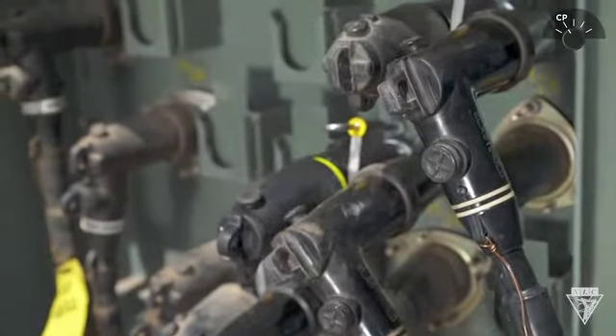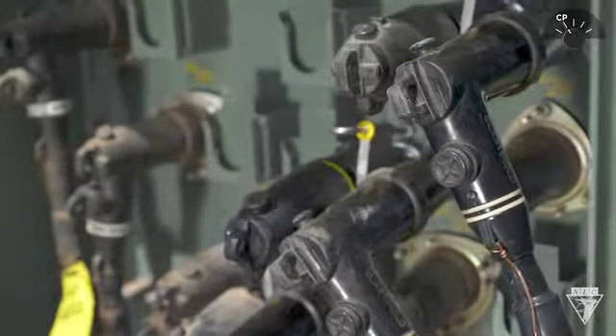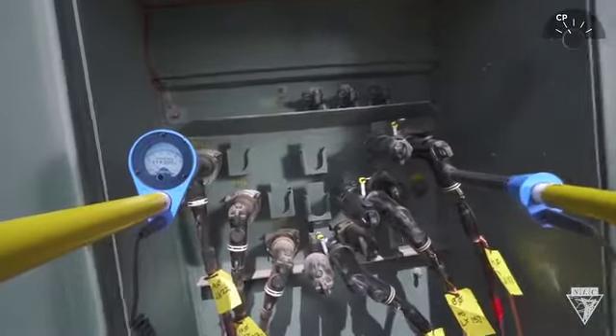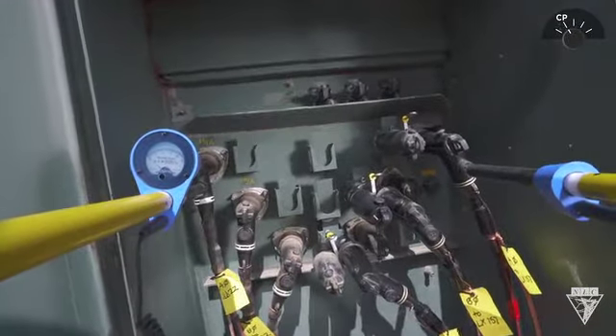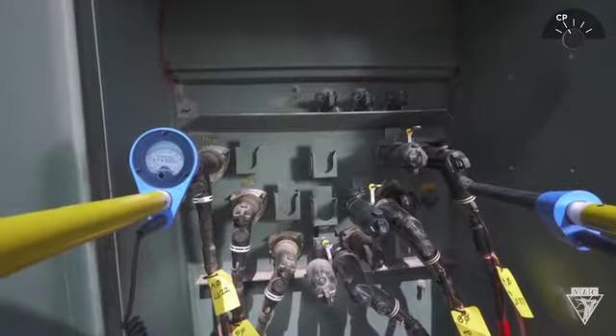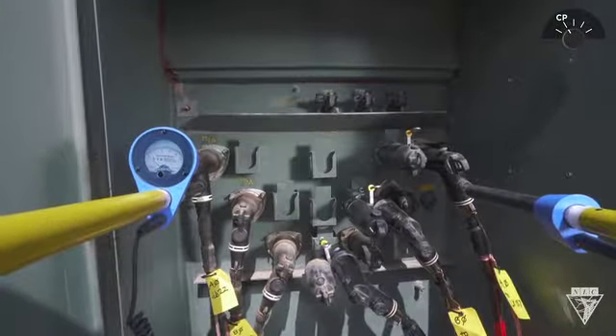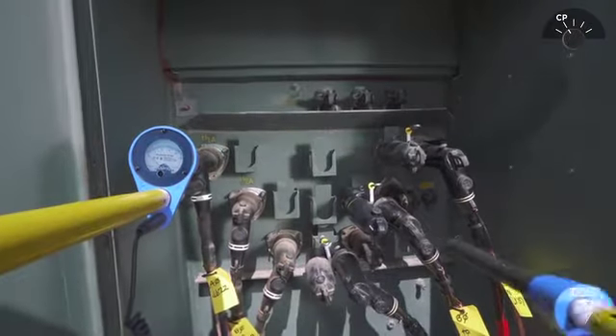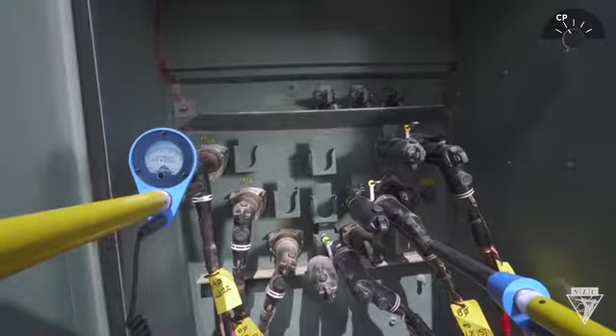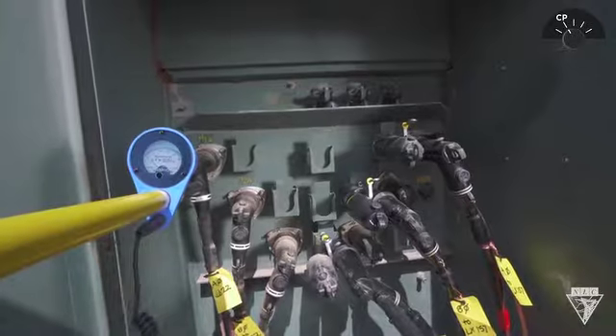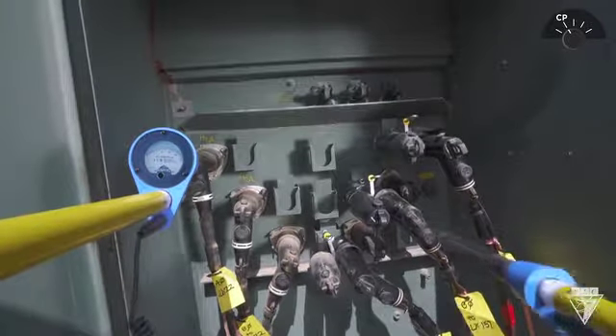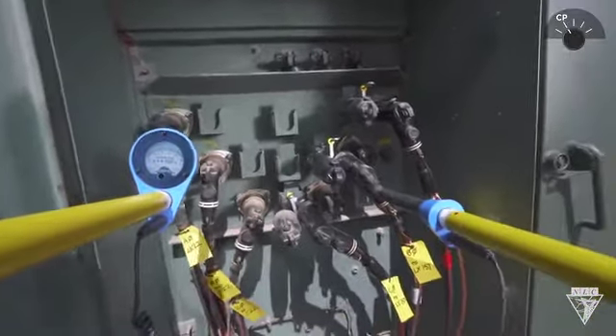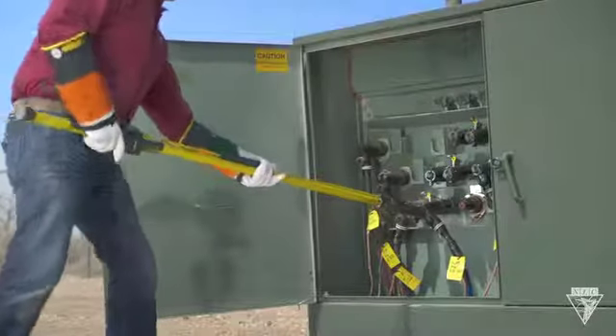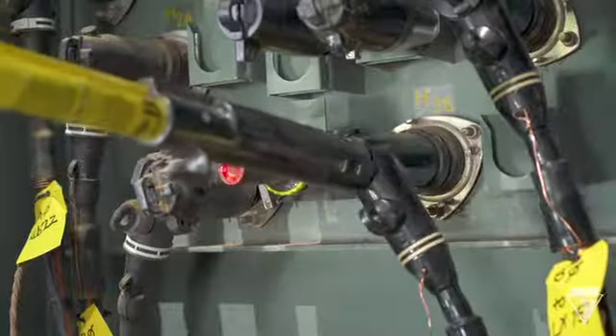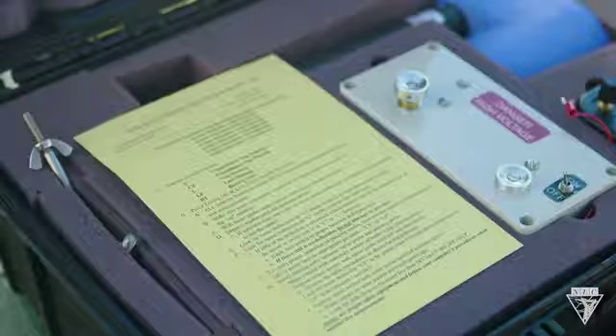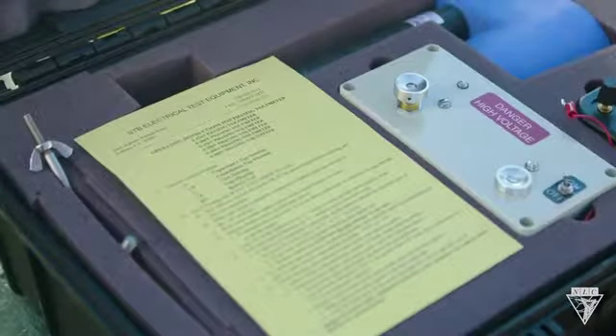To do this, remove the caps on the test points using a live line tool. Now, take both probes and touch them to the capacitance test points on both ends of the same phase. A 0 reading means the phases are in sequence, or the meter is malfunctioning. To ensure the meter is working properly, a cross-phase check should follow any 0 reading. Once the proper phasing sequence over all open points is proven, the line can be closed. Always follow manufacturer specifications and your company's guidelines when checking phase sequence.